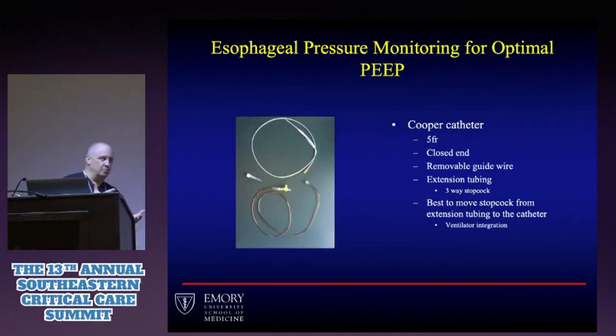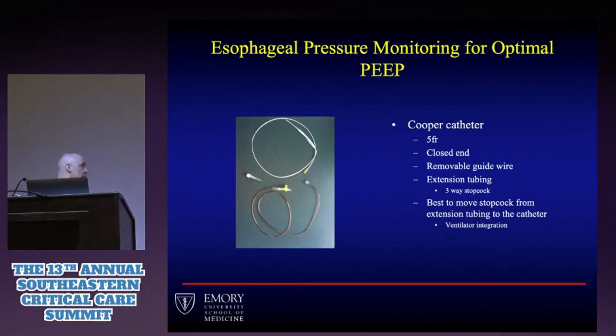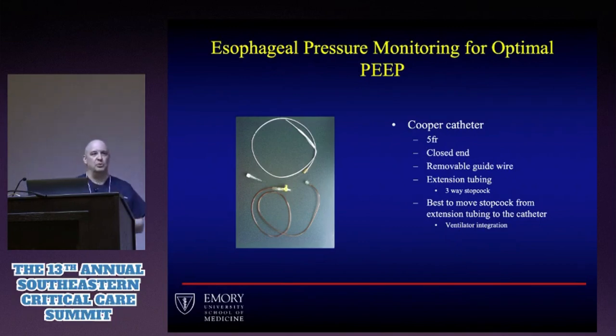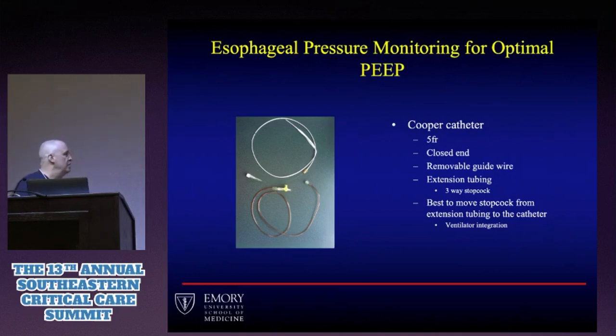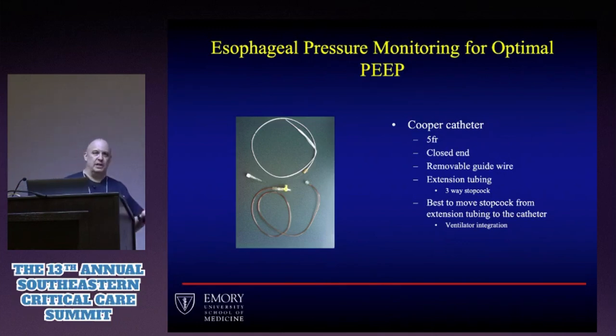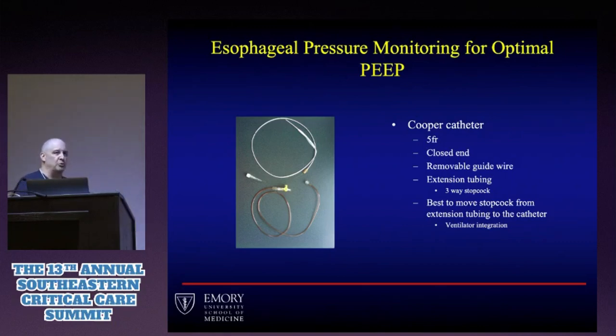The catheter itself is a 5-French catheter costing about $30, so it won't break the bank. It's closed on the end, so you can't infuse anything through it or put material in the wrong place. There is a removable guide wire — many facilities recommend leaving it in place in case the catheter needs repositioning, because once you pull it out, it won't go back in. It comes with extension tubing and a three-way stopcock.